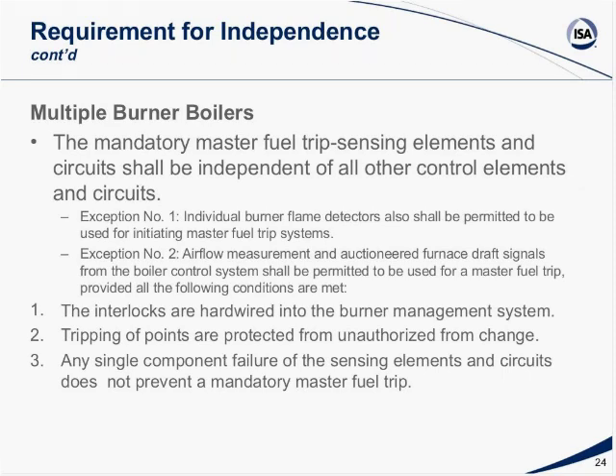A little bit is a repeat, but it's highlighted under multiple burner boilers. Individual burner flame detectors shall be permitted to be used for initiating master fuel trip systems. Airflow and furnace draft analysis from the boiler control system shall be permitted to be used for a master fuel trip provided all the following conditions are met. The interlocks are hardwired in the burner management system, which is what I just talked about. Tripping of the points are protected from unauthorized changes. Any single component failure in the sensing elements and circuits does not prevent master fuel trip.